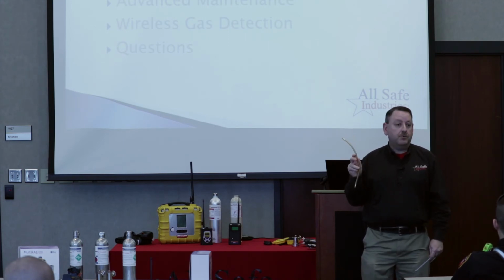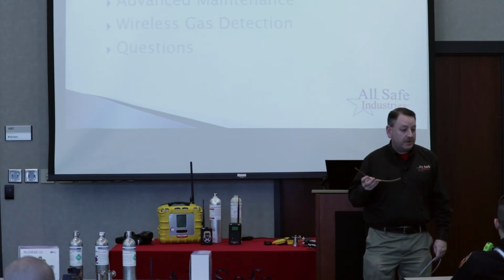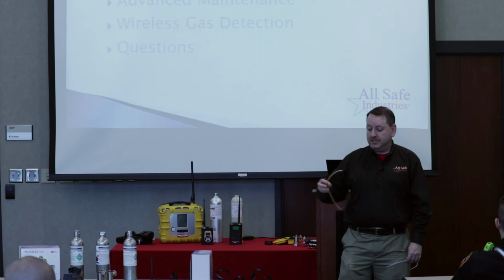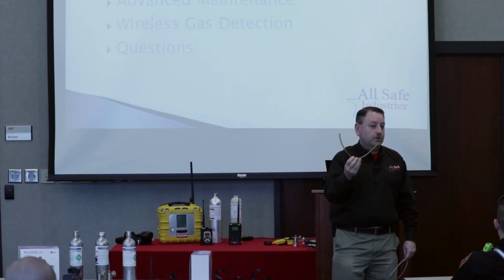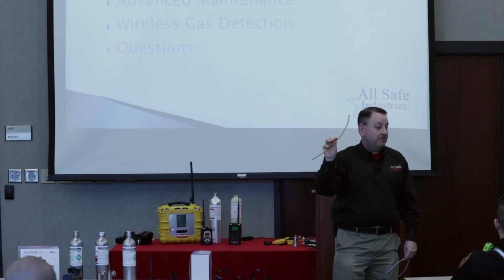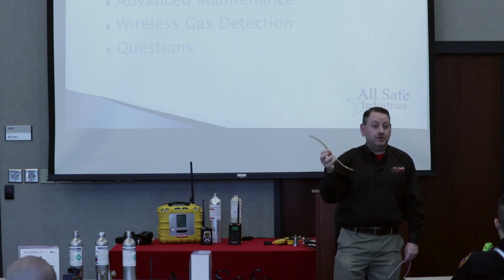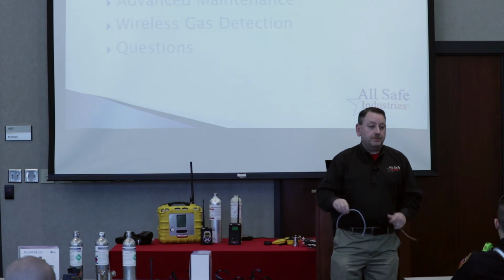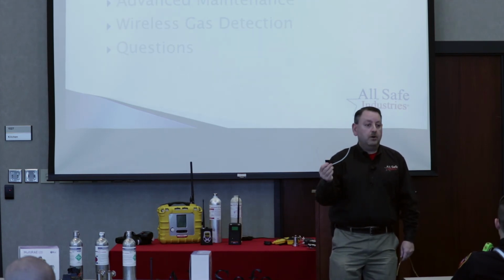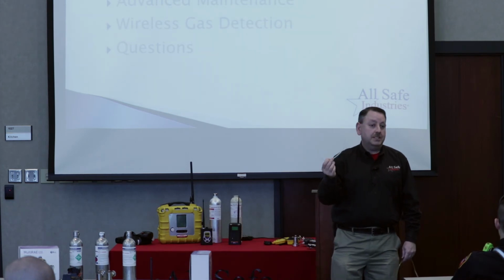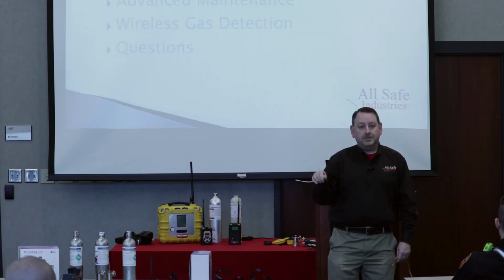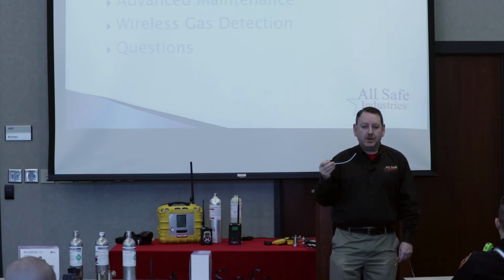The clear tubing is fine for confined space type gases, your oxygen, your flammable gases, simple gases like CO and H2S, because you'll notice this tubing will actually absorb some of the gas. And so I pulled this out of service from a fire service, and you can see that it's turned practically coffee color because it just shows that this tubing will absorb some gas. If you're trying to measure VOCs, volatile organic compounds, in very low parts per million, you're going to want to use Teflon tubing. Again, it's a brand name, but if you looked at this under a microscope, it's a very slick, non-porous surface. And so if we're trying to measure 5 ppm benzene, I need to run that sample through Teflon tubing because it's going to give me the better opportunity to get the whole sample to the sensor in your meter.